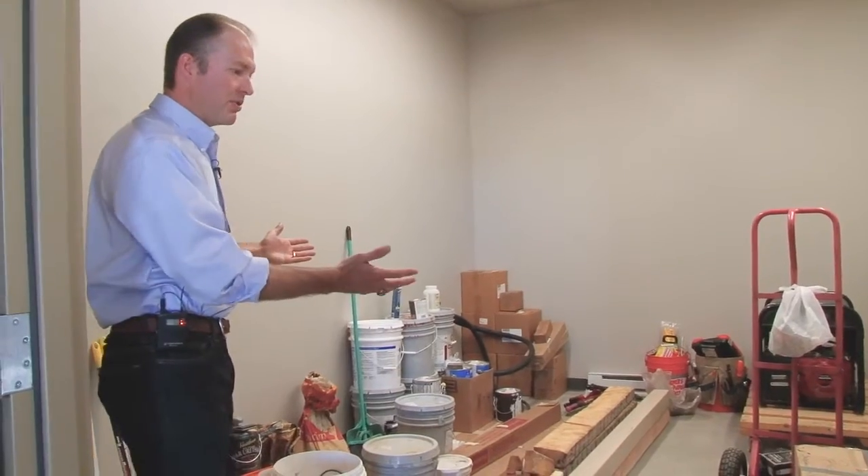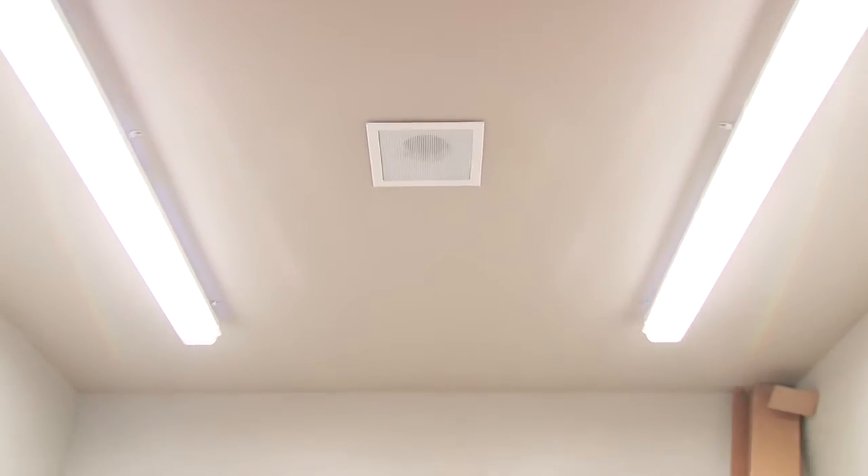In this room there's going to be paints and all sorts of chemicals. We're going to exhaust this room, so when the door is closed it's actually not going to interact with the main space. It'll pull some fresh air through a cross vent, and that way all the smells are going to be out of the building. The same goes true for our bathrooms, showers, and kitchens. We bring all that moisture, all the smells — which could be volatile organic compounds such as gas and paints — and we send it out of the building. We don't let it run around our houses or our buildings.